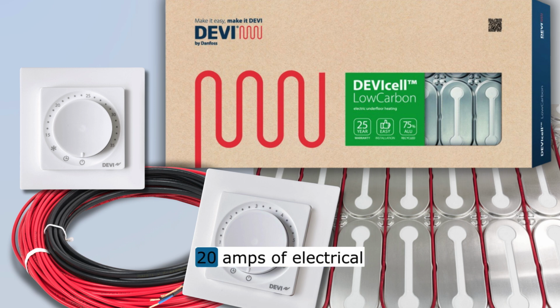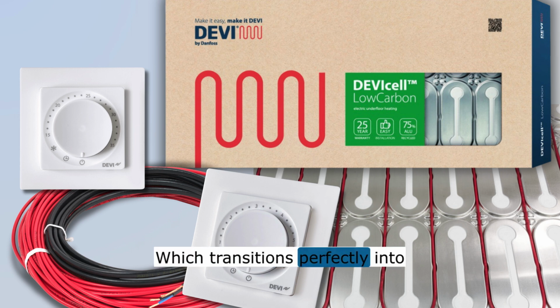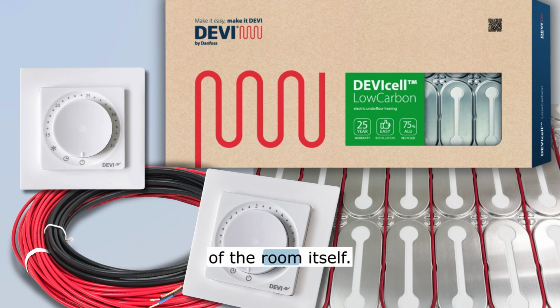If you tried to push 20 amps of electrical current through a thin 1.5 millimeter wire, that wire cannot handle the flow. Like a traffic jam. Exactly. It experiences too much friction, essentially acting like a heating element itself. The wire will melt the insulation inside your drywall before the 20 amp fuse ever realizes there's a problem. Oh, wow. So matching the fuse to the wire gauge ensures the breaker trips before the wire physically melts inside your wall. Spot on, which transitions perfectly into the overall thermal limits of the room itself.